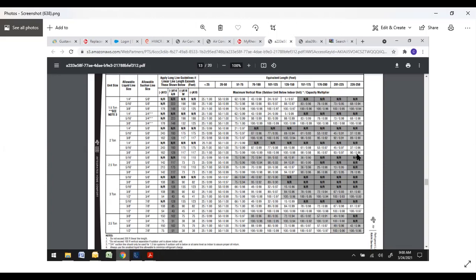You can go all the way pretty much as far as you want to, and you're fine. So it gets more critical with the larger the tonnage. It does make a difference. If you start trying to skimp on the line size, smaller ones you can get away with a little bit more. The bigger the units, you try to get by with anything less than a 3/8, you'll end up with problems out of the gate.